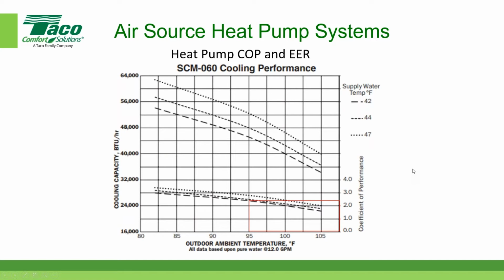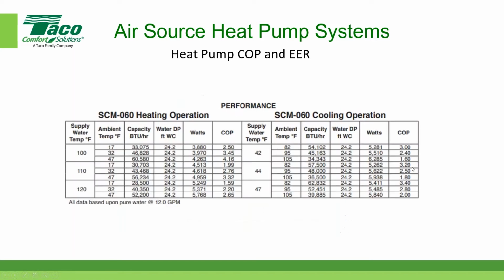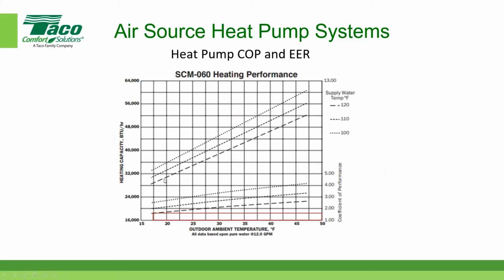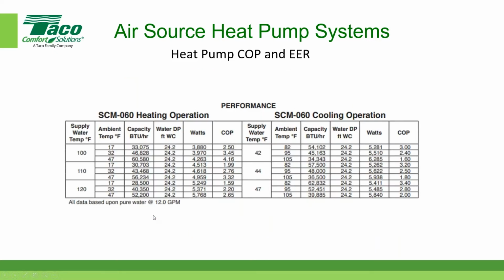So that's the cooling performance. Let's look at the heating performance for the same unit. And so we're looking on the left side of the chart this time. At the left side of the chart, let's say we're down here to 17 degrees Fahrenheit. So let's go back up here. Let's say we wanted a supply water temperature of 120 degrees, and we had an ambient temperature of 17 degrees. We could provide from this manufacturer 28,500 BTUs per hour. And if you notice, the COP is 1.59. So even though it's 17 degrees, it's still above 1, which is really good.